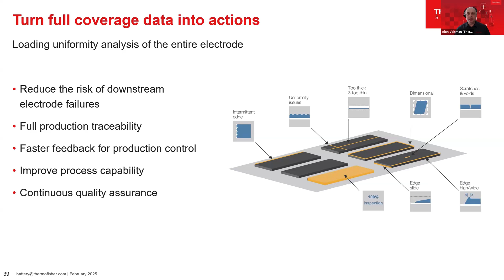The example screenshot here from the mass profilometer HMI shows two patches of NMC cathode. This data was collected at 60 meters per minute line speed. Mass profilometry data makes it easy for the operator to see that the loading is high and out of spec in the bottom right section of the lower patch. A closer look also reveals what appears to be a streak in the machine direction.